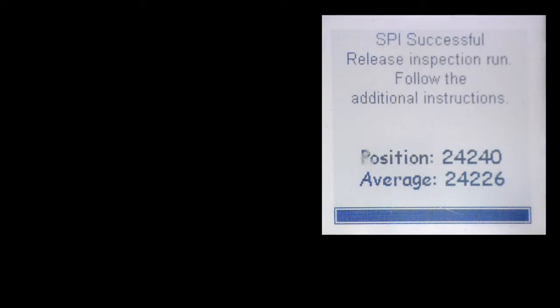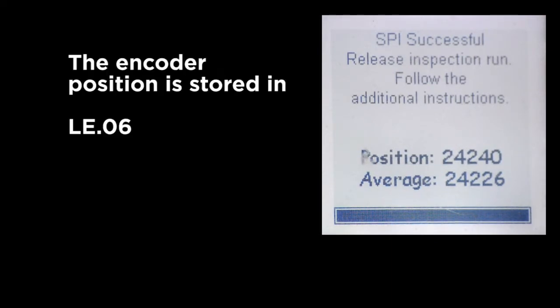When complete, the drive will indicate success and show the last position. It'll take an average of all those positions and save that position into the LE06 encoder pole position parameter.